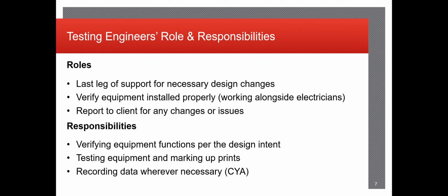Like I said, we verify the equipment is installed properly. We work alongside electricians to verify this. We go through each and every circuit, each and every piece of equipment that gets installed, test it, functionally test it, and then put it into service at the end.